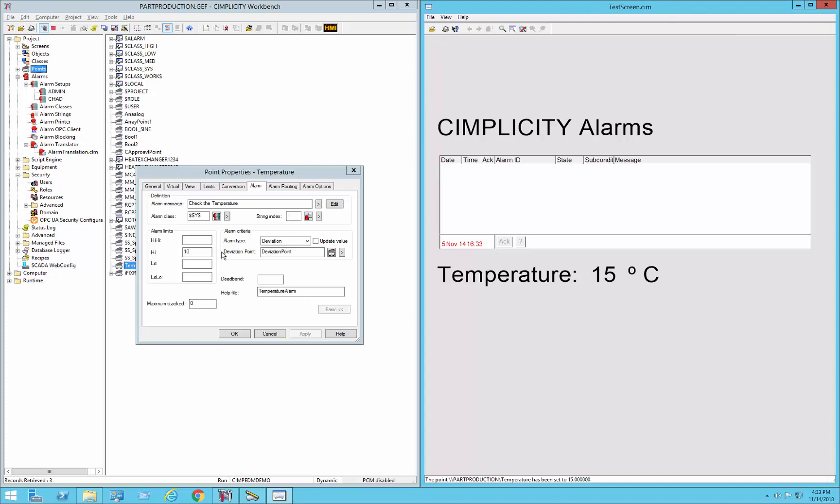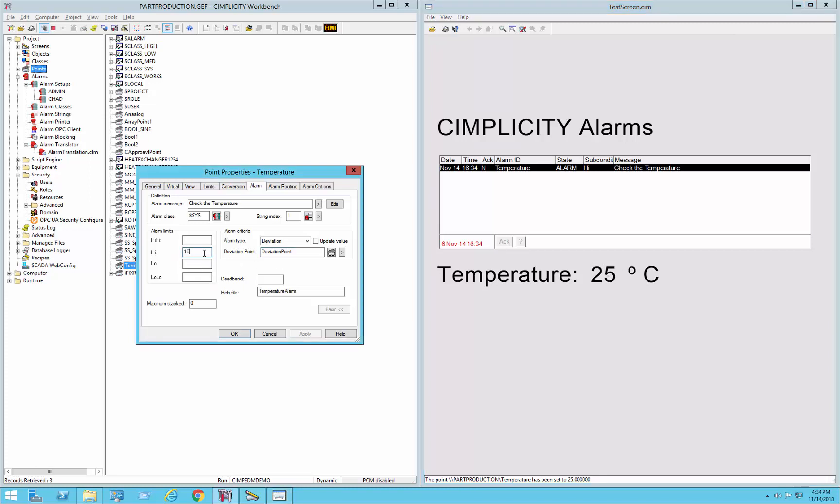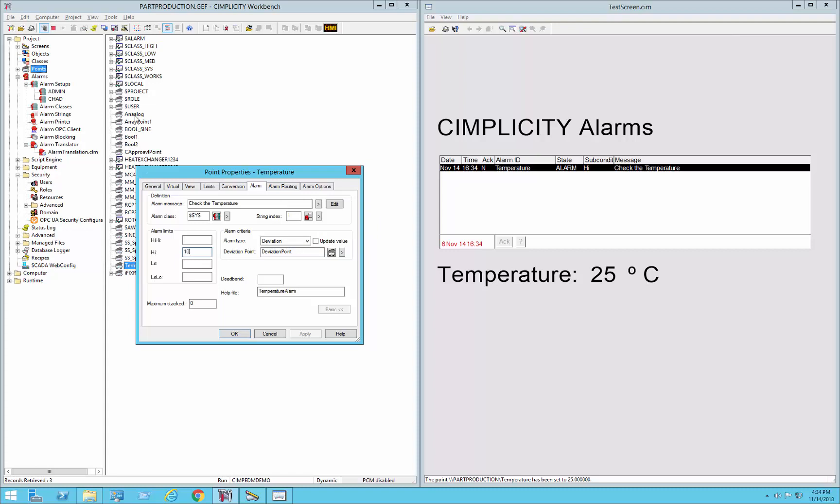So we don't have an alarm right now. Currently, we're at 15, and our deviation point is at 10, so if we go to 25, our deviation will be 15, and that will put us in a deviation alarm situation where we differ from the deviation point by more than the value of the deviation point. So if you look at the deviation point in the database, you'll see we set it to 10. So when we go outside of the range of the difference between our point and the deviation point by whatever limits are here, we'll get a deviation alarm.